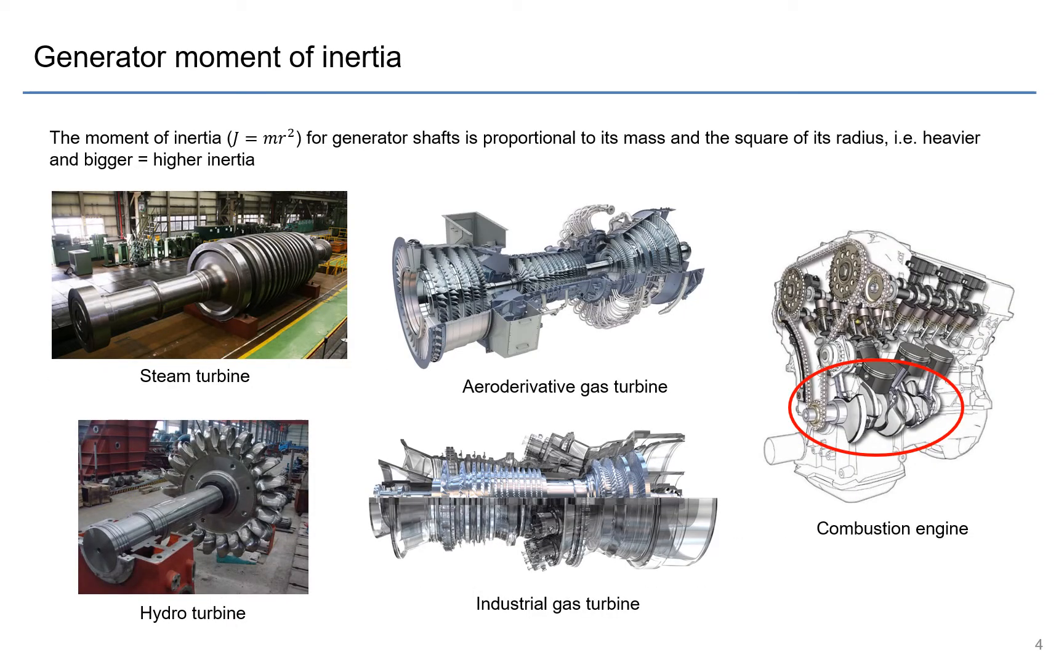So the moment of inertia for a generator is probably something that's familiar to you guys already and something that you would find on a generator data sheet. And from the equation J equals mr², for generator shafts the moment of inertia is proportional to its mass and the square of its radius. So the heavier and the bigger a generator shaft, then the higher the inertia. And you can see here typically with steam turbines and industrial gas turbines you may have some of the higher type inertia constants, whereas the aeroderivative gas turbines, which are as the name suggests derived from aeroplanes, they're much lighter and have lower inertia. And hydro turbines depending on its type can have quite high inertia as well.